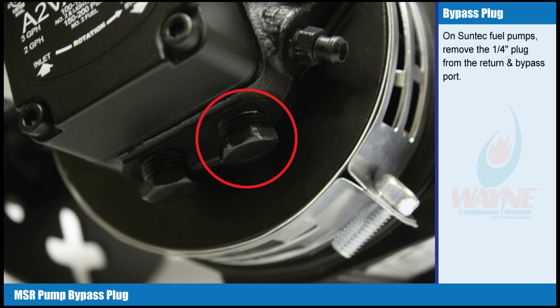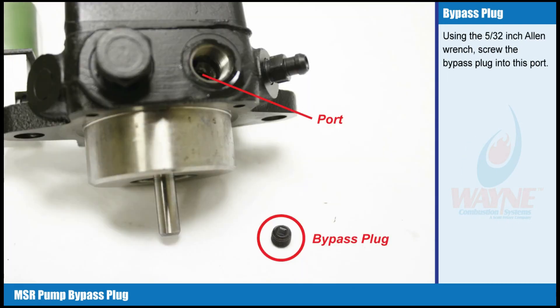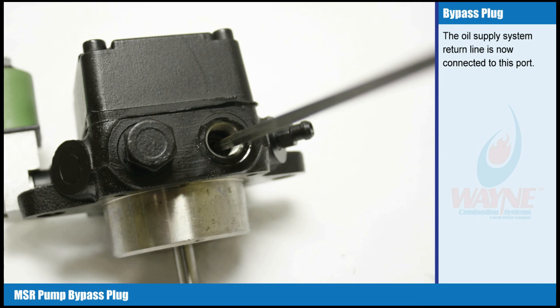On Suntec Fuel Pumps, remove the one-quarter inch plug from the return and bypass port. Using the 5/32 inch Allen Wrench, screw the bypass plug into this port. The oil supply system return line is now connected to this port.